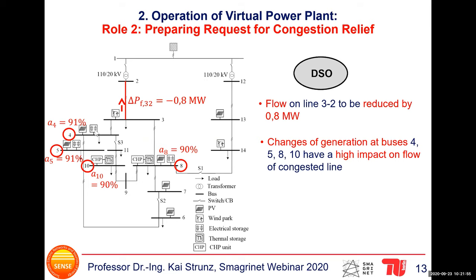But the virtual power plant of course needs to know by how much service is needed. So here the 91%, that information coming from the grid operator tells that 91% of the power injected here will actually flow on the line between 3 and 2. And 90% of the power injected into the bus number 8 will also flow from 3 to 2. So not everything that is injected here will actually arrive on the line. So we will actually need to reduce our power here by more than 800 kilowatt. So by more than 0.8 megawatt in order to have an effect. More strictly speaking, it would be 0.8 megawatt divided by 0.91. If we do that, then we achieve the effect desired.